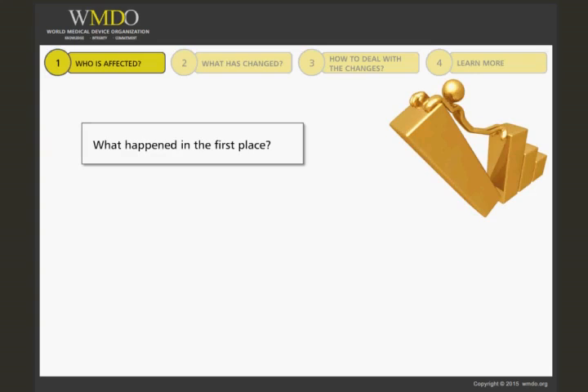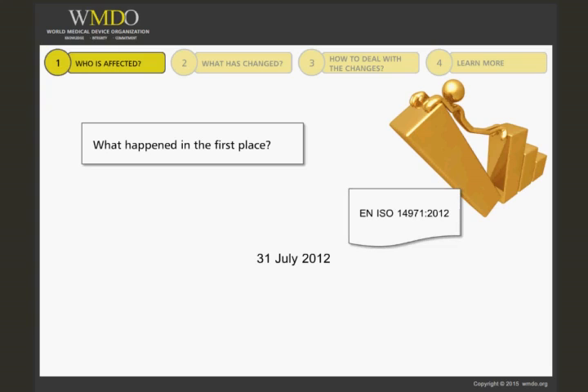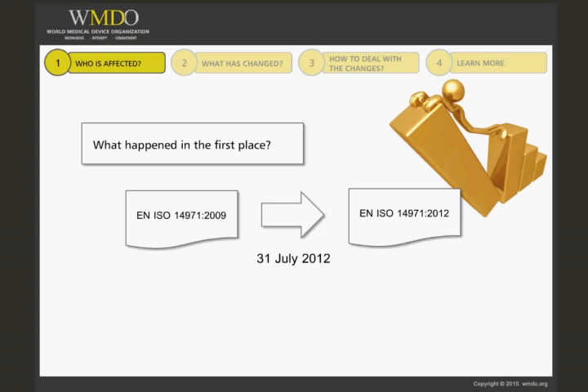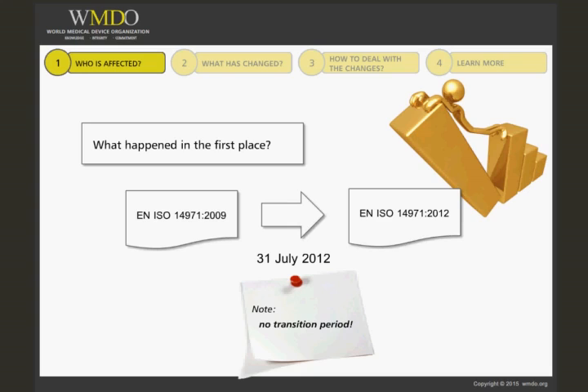Let's start with what happened in the first place. On the 31st of July 2012, EN ISO 14971:2012 regarding the application of risk management of medical devices replaced EN ISO 14971:2009 as the European harmonized standard. This change was effectuated with a transition period of zero days, which is very unusual. The reason for this is that EN ISO 14971:2012 is not based on any new ISO publication. Instead, CEN — the European Committee for Standardization — added its interpretation of what it believes to be shortcomings in ISO 14971 relative to the European medical device directives.